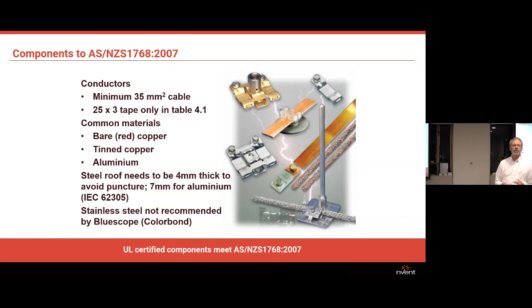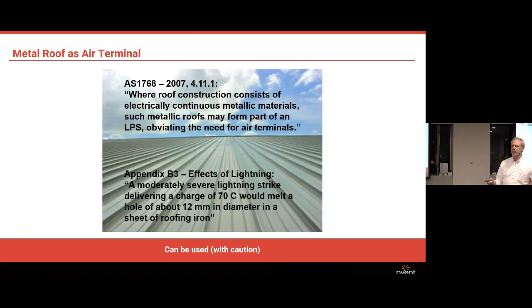And that's saying stainless steel is not recommended by Bluescope, which is an Australian roofing supplier. AS 1768 2007, 4.11.1 states where roof construction consists of electrically continuous metallic materials, such metallic roofs may form part of a lightning protection system, meaning you don't need air terminals.